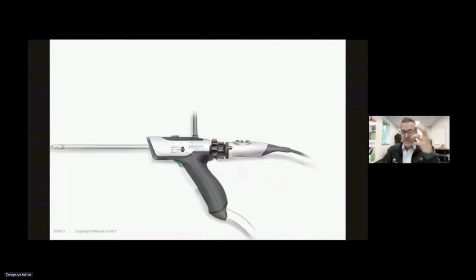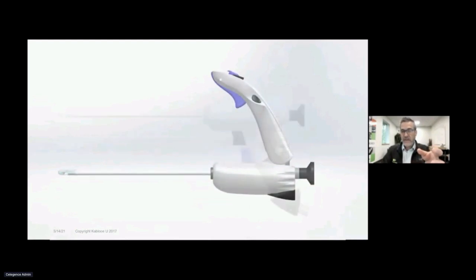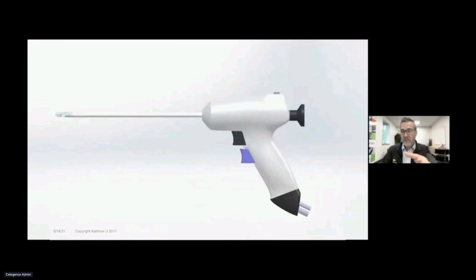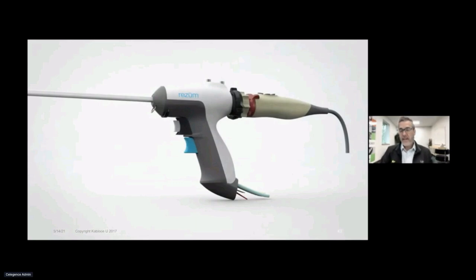And we start taking a look at, can we take last minute configurations and learn from what's worked and what hasn't worked, and put it into a final configuration so we can go into beta testing. And this is what the final configuration turned out to be, that had all those pain points that were mitigated with design efforts and design changes. We mitigated those pain points, created design criteria or design inputs in our user interface requirements, our user interface specification document. And then we designed to that and we made those changes, and this is what the device turned out to be. So this was our beta prototype device that would now go into your design validation.